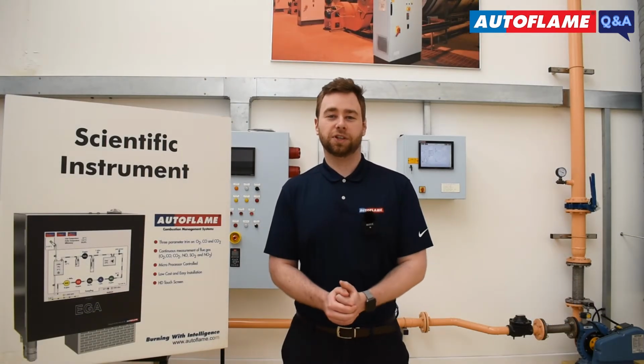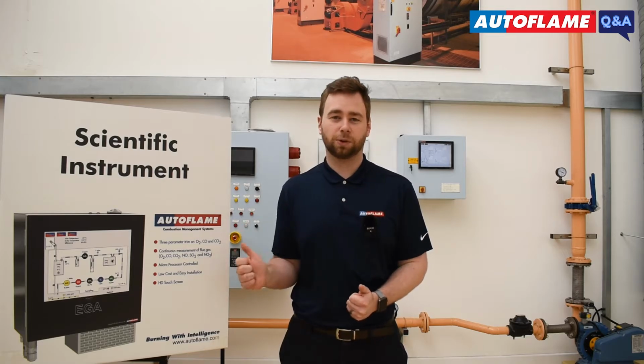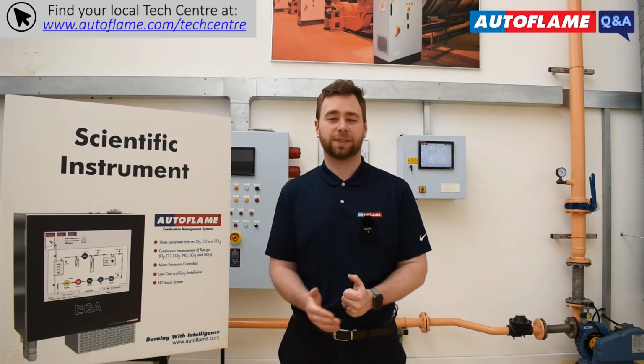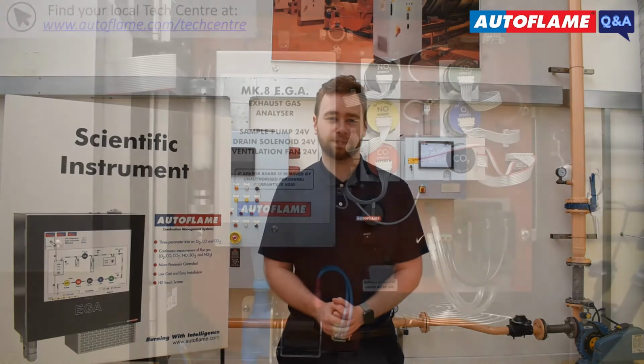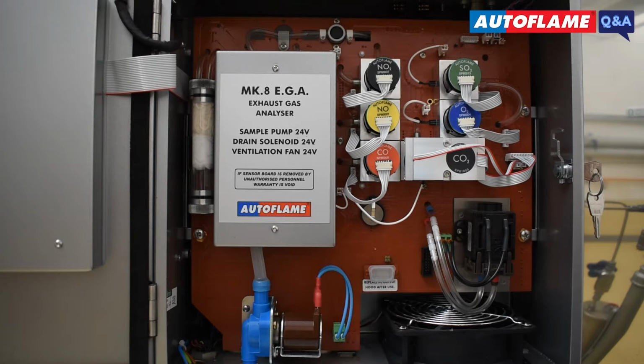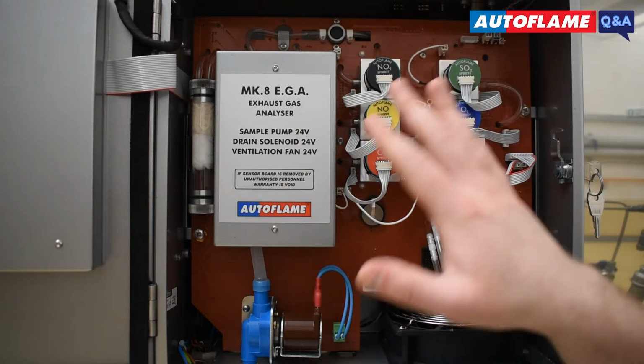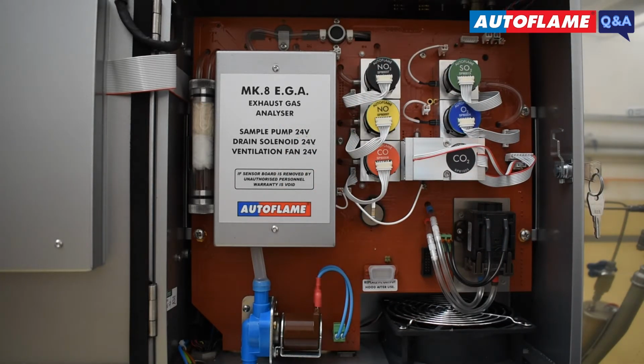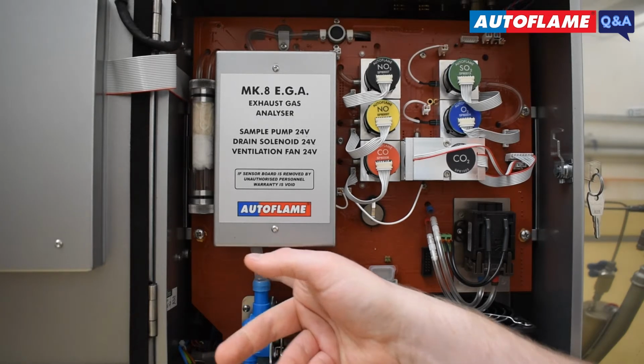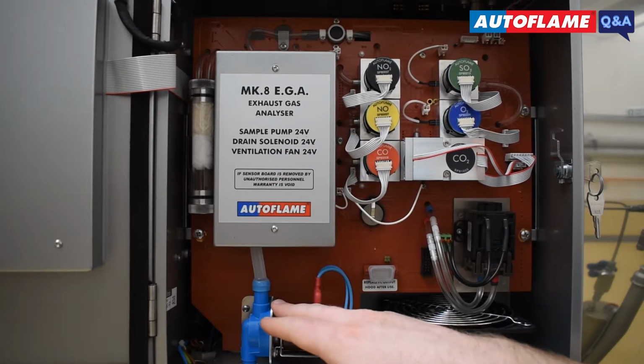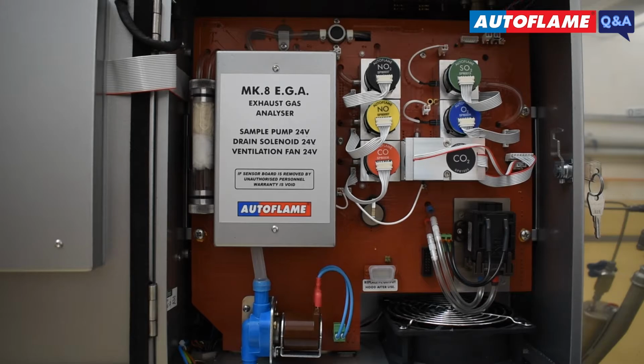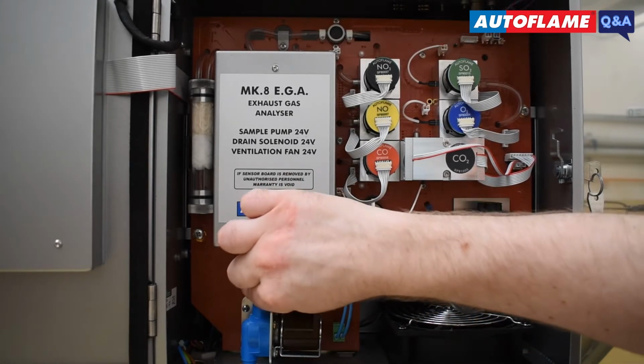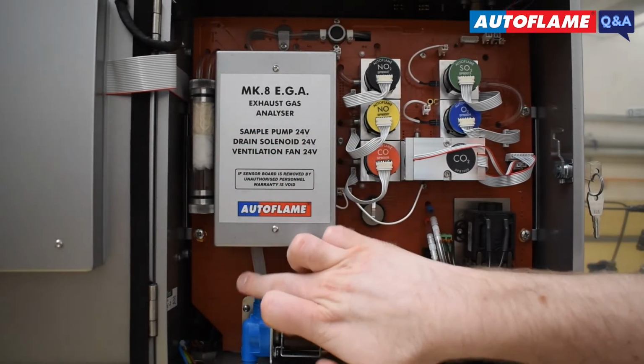Now that you've removed your EGA, we strongly recommend using the original box that your EGA came in for optimum protection during shipping. If you don't have your original box, your local Autoflame Tech Centre can provide you with one. It's also beneficial for our repair engineers if you give the EGA a quick wipe down to clear any dust. Before placing the EGA in its box, remove the tube from between your chiller block and your drain solenoid to prevent the EGA from flooding. You can use a rag to absorb any moisture that was built up in the chiller block, tubing and the drain solenoid.